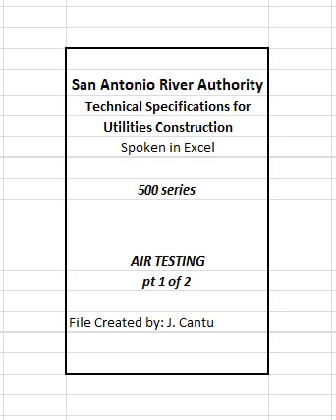Allowable test times for selected type pipe less than 36 inches average inside diameter is shown in a table. The heading titles are pipe diameter, minimum time, length for minimum time, and time for longer length. An owner may stop a test if no pressure loss has occurred during the first 25% of the calculated testing time. If any pressure loss or leakage has occurred during the first 25% of a testing period, then the test must continue for the entire test duration as outlined above or until failure.